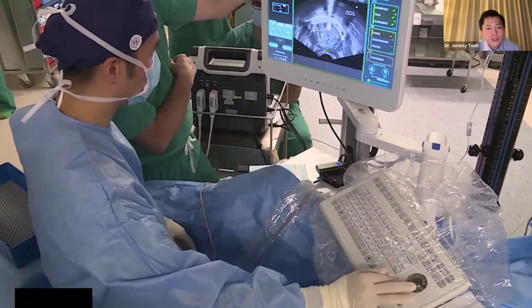So we tap on the pedal, and you can see the water jet being delivered. It's like a test dose, and then we can calibrate the system so that the system knows where the water jet is going to come out. And then now we try to plan the actual ablation template. So we retract the ultrasound until we see the widest area of the prostate, and then we plan the angle of ablation. If the patient has a median lobe, we can plan an additional median lobe template.